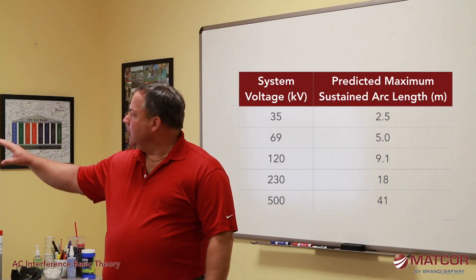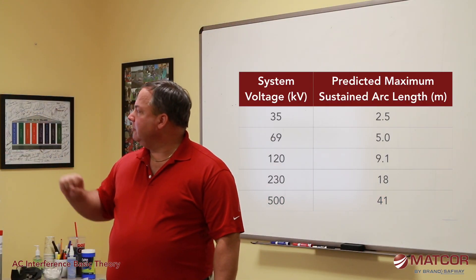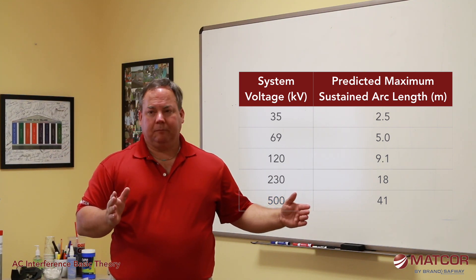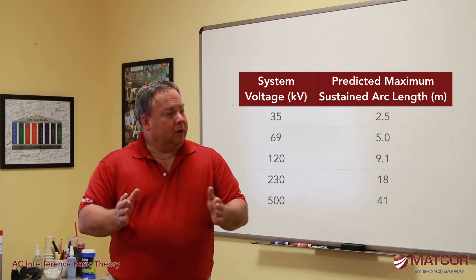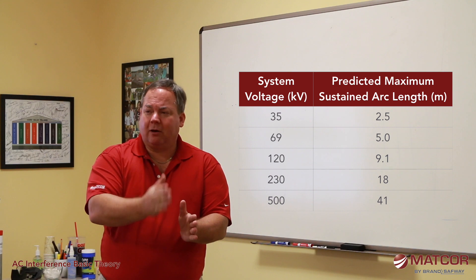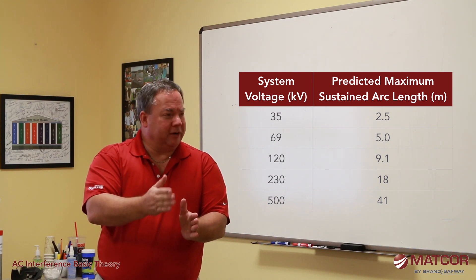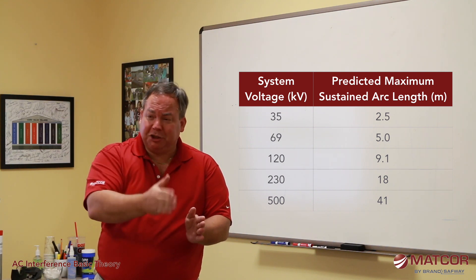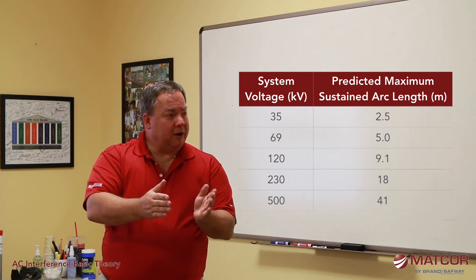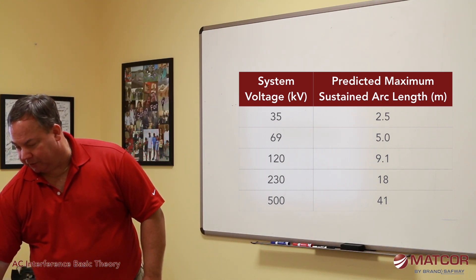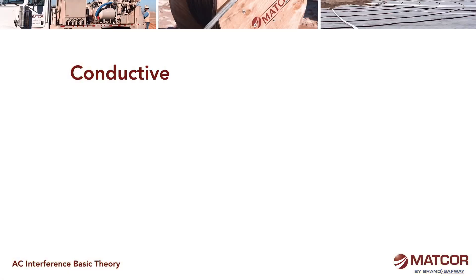Depending on soil resistivity and the voltage of the system, we can predict how far arcing can occur through the soil. If the pipeline is within that distance, we have to put some sort of shield in there that's going to take that arc before it gets to the pipeline — catch it and dissipate it. So we have to put something as a shield between the pipe and the tower footing where these faults occur.